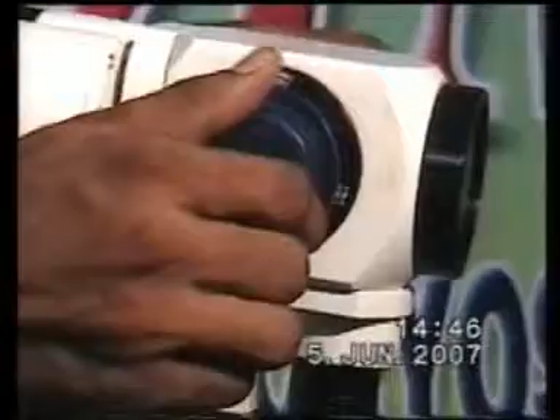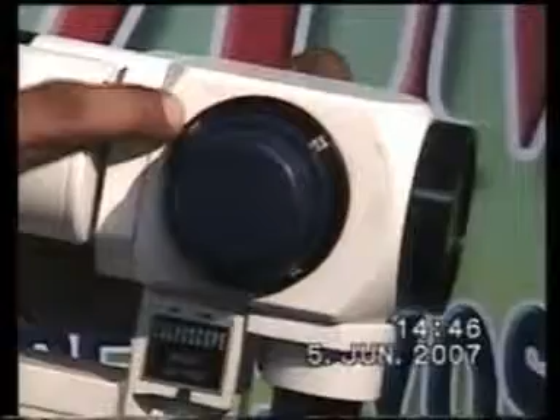So in this lens portion, this knob is meant for magnification. There is a small dot over here. So the 10x or 5x is mentioned, and it should be kept near the dot. It should be maintained like that. Now this is for interpupillary distance. To maintain the interpupillary distance between our eyes from 54 mm to 72 mm, this is to be widened or brought closer. This is for fine focusing of our eye. These two things are to be independently controlled.